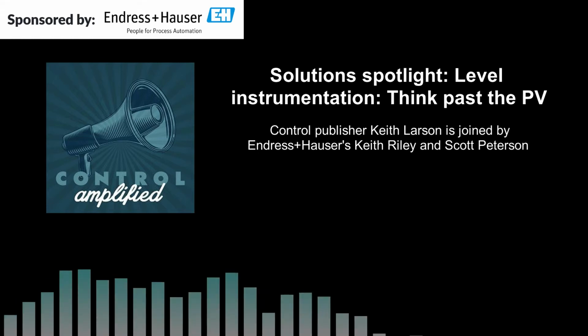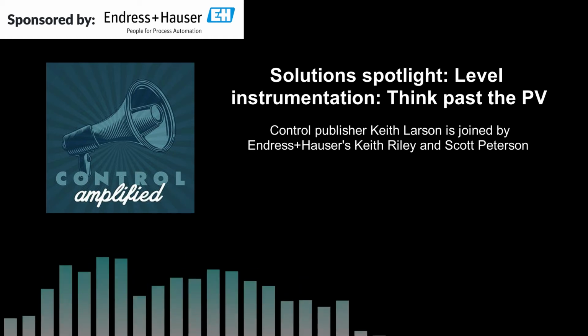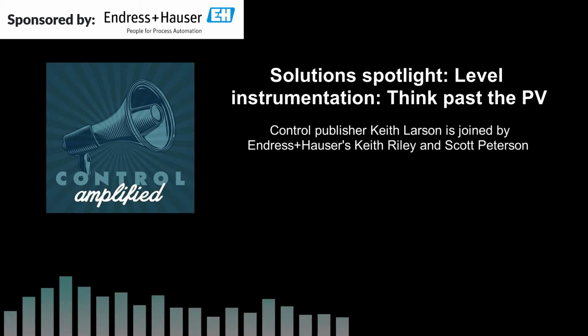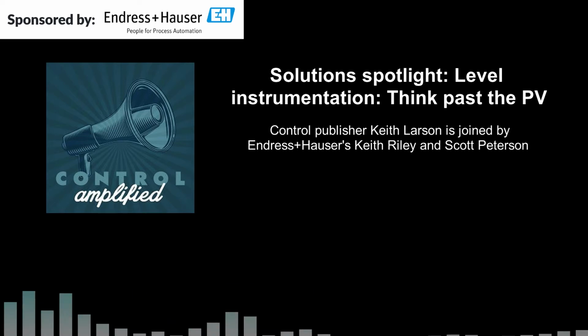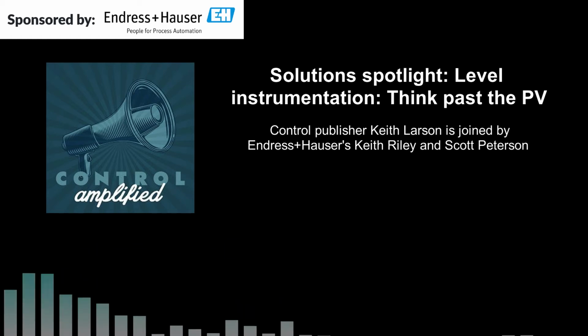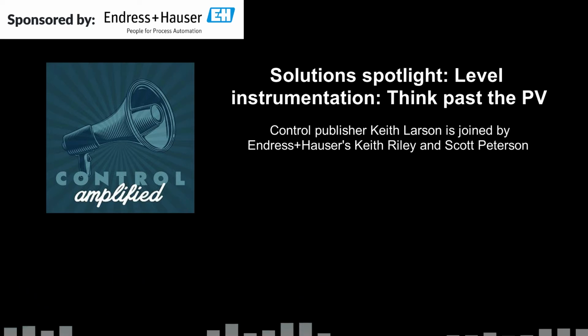Thank you, Keith. Well, let me start by saying when I think of improved safety, I've got two categories: the process safety, which you referred to, and also personal safety. So I think there's two different things to look at. If we start with the process safety or a safety instrumented system, similar to your first question, to be honest, there's a lot of parity in the market. Any good manufacturer, your lambda DU values from a safety standpoint are going to be extremely close. So the real thing to think about is, how can I use this instrument to reduce my systematic failure, or the risk of systematic failure, I should say, which is really more of a human error type aspect, which there's no preventing it from ever happening, but you can mitigate it.